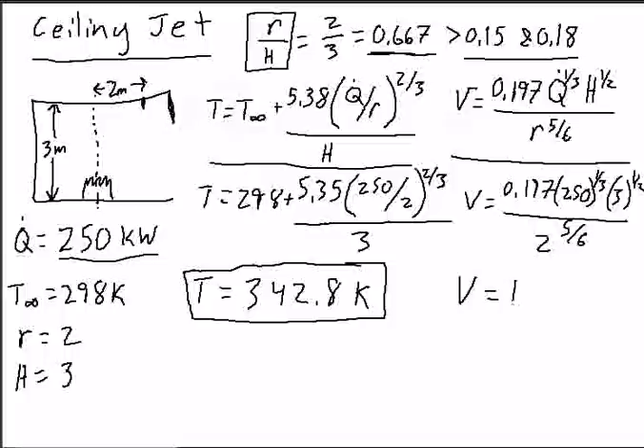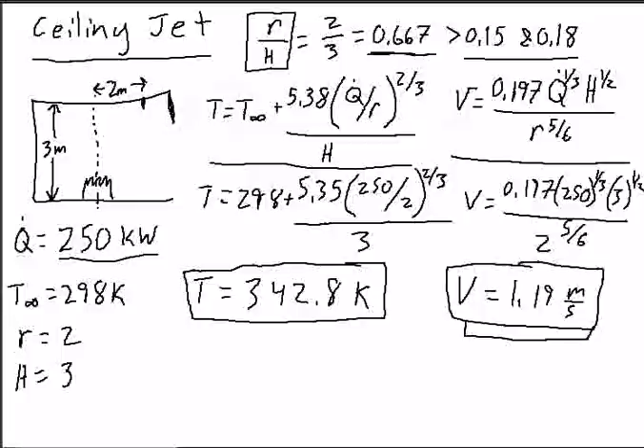So our velocity would equal 1.19 meters per second based on the units we're using here. And so once again, you want to think about is this reasonable? And close to one meter per second of a buoyancy-induced velocity is pretty reasonable in the literature that I've read. So as you get more experience, you can make those determinations as well.